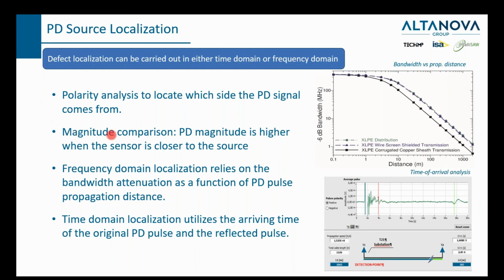And the second is magnitude comparison. Apparently, PD magnitude is higher when the sensor is closer to the source. That requires multiple sampling. A typical example is if we have a row of switchgear cubicles, and there is a lot of crosstalk when we test the cubicles. So the best practice is to test all of them and find the panel with the highest magnitude, and most likely that's the PD source.